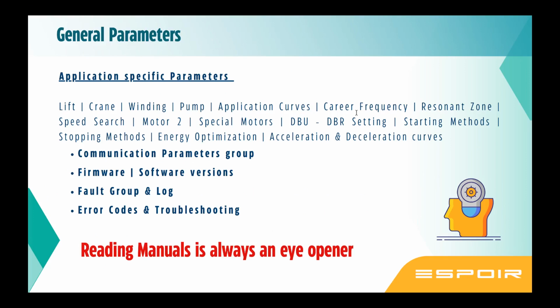There are very detailed communication parameter groups, firmware and software versions, and a clear fault group. And you can watch the fault codes: the trend of a fault, and what all the faults are that have happened so far. It is a big log. You can log in and see what the particular fault was, what caused that fault, and what the remedy is.